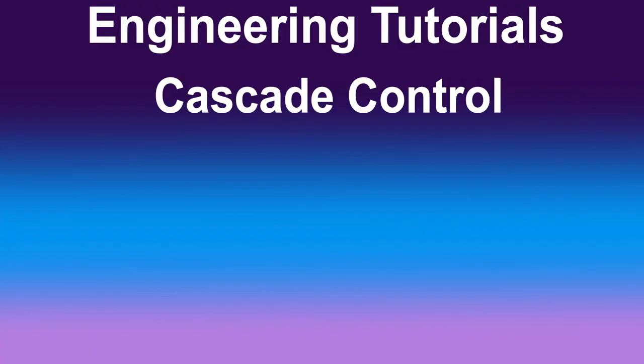External feedback to prevent wind-up in cascade. External feedback, a method to prevent wind-up by providing an external feedback signal to the integral term of the controller. This ensures the controller output remains within its operational limits, preventing saturation and maintaining control stability. These sections provide detailed information on specific applications of cascade control and measures to prevent integral wind-up, ensuring effective and stable control in various industrial processes.